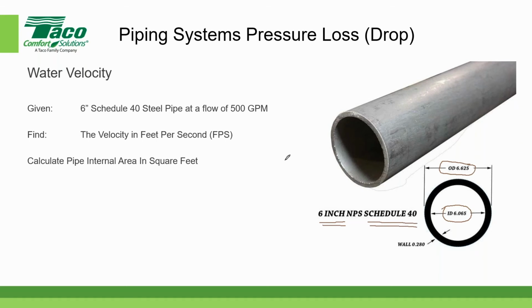So whenever we think about velocity, we always have to think of the inside diameter, because when it comes to piping systems, especially steel piping systems, they're all the same outside diameter. In other words, a 6-inch pipe at Schedule 40 has the same outside diameter as a 6-inch pipe at Schedule 60 or Schedule 80. But the inside diameter changes because the wall thickness changes. In our case, for the Schedule 40 pipe, the wall thickness is 0.280 inches. Okay, having said that, let's go to the next piece.